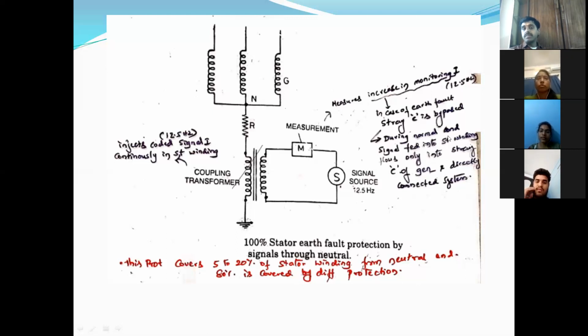During normal conditions, that means when there is no fault, the signal fed into the stator winding flows only into the stray capacitance of the generator and the directly connected system. During LG faults, this signal goes to the winding where the capacitance is bypassed, and that is monitored continuously. Whenever a fault occurs in that 15 to 20%, it will be detected. So this protection covers 5 to 20% of the remaining stator winding, that means the unprotected winding from neutral to end. 80% is covered by differential protection, and the remaining percentage is covered by this type of scheme. So let us see a problem on this.